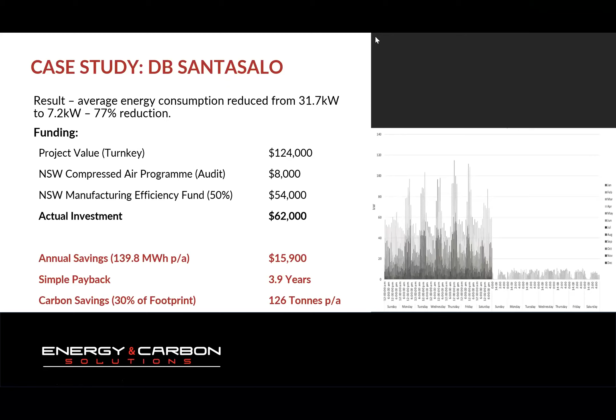Yeah, certainly. When we specified the machine - when you put heat recovery into an air compressor, like a screw compressor, it's done on the oil circuit. We bought those machines because we needed to upgrade, and we specified this as part of the package when we bought them. So most of the heat load is actually coming out of the oil - very little comes out of the actual hot air. It's the recirculating oil loop, and the heat exchanger in those goes between the air end and the aftercooler.